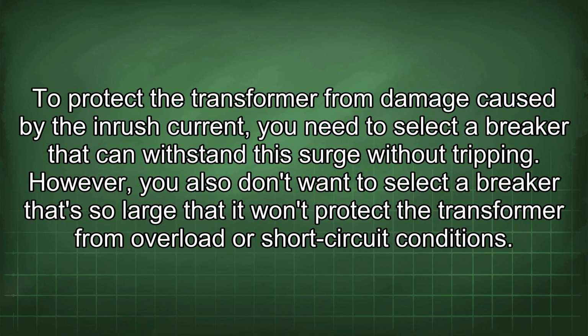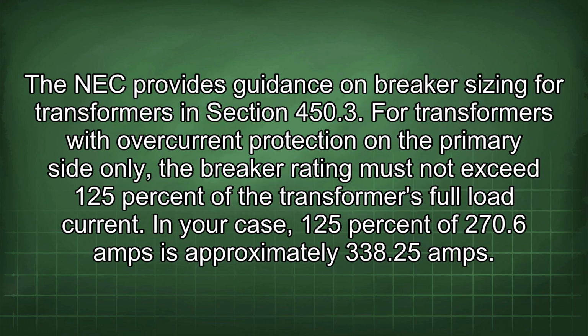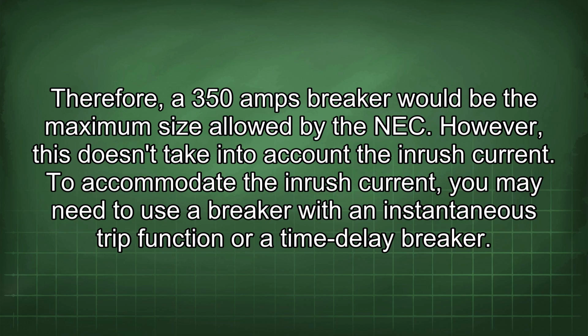To protect the transformer from damage caused by the inrush current, you need to select a breaker that can withstand the surge without tripping. However, you also don't want to select a breaker that's so large that it won't protect the transformer from overload or short circuit conditions. The NEC provides guidance on breaker sizing for transformers in section 450.3. For transformers with overcurrent protection on the primary side only, the breaker rating must not exceed 125% of the transformer's full load current. In your case, 125% of 270.6 amps is approximately 338.25 amps. Therefore, a 350 amp breaker would be the maximum size allowed by the NEC.